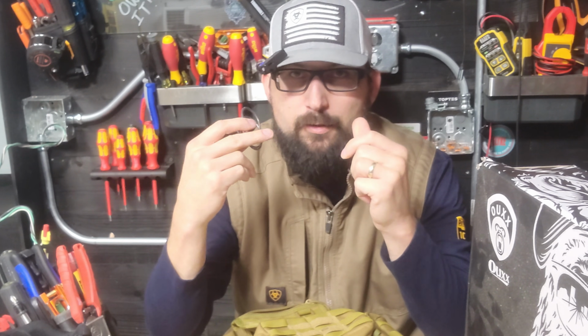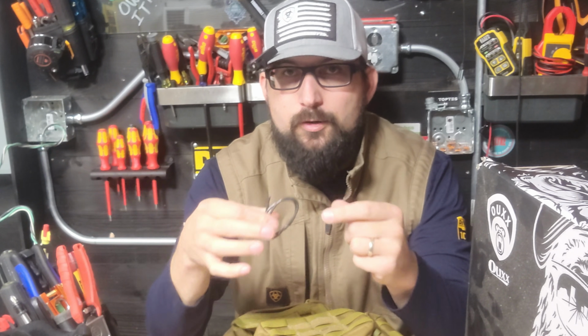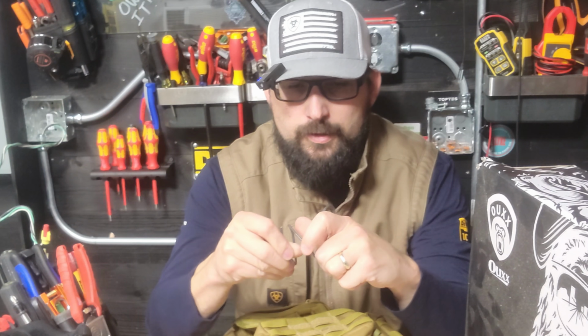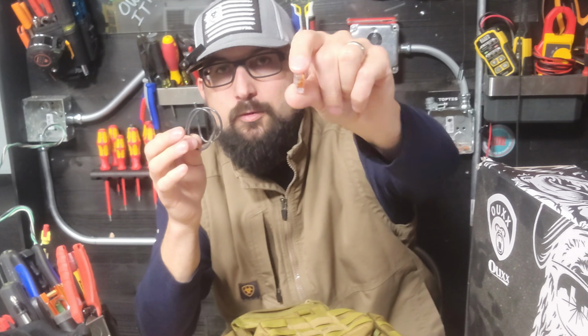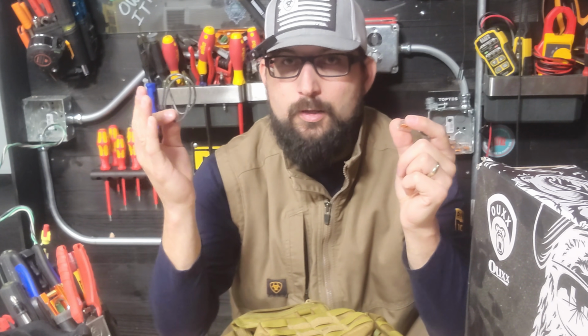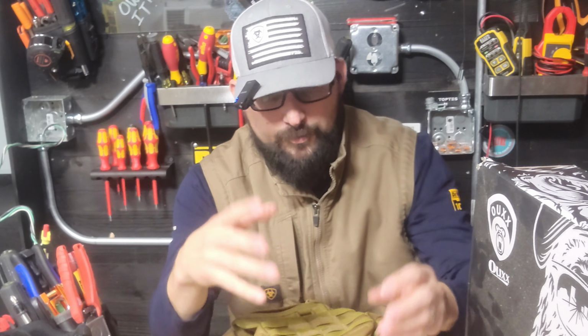Basically, your emergency light will turn on when power fails in that area, so it's never dark in that area. And a little jumper goes a long way when explaining that, because you can open up the panel, you can take two circuits that are not tied with each other, put them underneath two of the spots of the Wago, and then add one piece of wire to one single breaker to tie all of it together. So I keep this on me now to help electricians out.